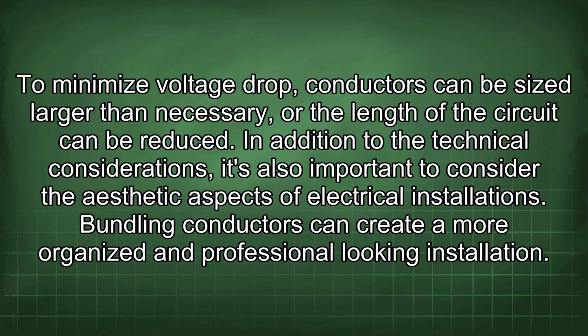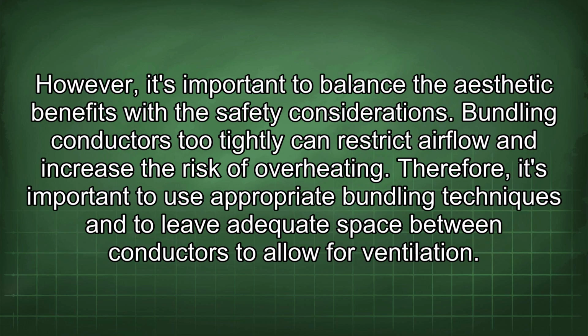In addition to the technical considerations, it's also important to consider the aesthetic aspects of electrical installations. Bundling conductors can create a more organized and professional-looking installation. However, it's important to balance the aesthetic benefits with the safety considerations. Bundling conductors too tightly can restrict airflow and increase the risk of overheating. Therefore, it's important to use appropriate bundling techniques and to leave adequate space between conductors to allow for ventilation.